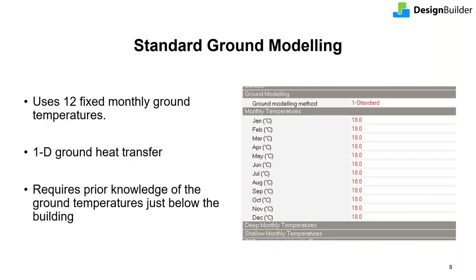Starting with the standard ground modeling. In the standard method, a set of 12 fixed ground monthly temperatures are used. These temperatures define the temperature on the outside boundary of the building's ground adjacent surfaces. Conceptually this is the simplest method since it is based on one-dimensional ground heat transfer. However, it requires prior knowledge of the ground temperature just below the building for accurate heat transfer calculations. Depending on the modeling case, these temperatures can be estimated using rules of thumb, but in practice knowing them accurately is rare.